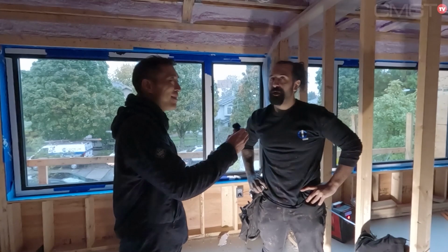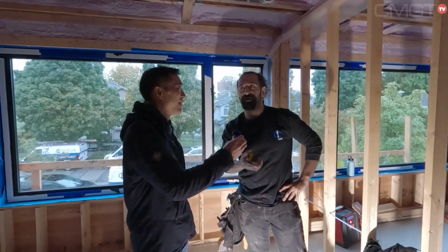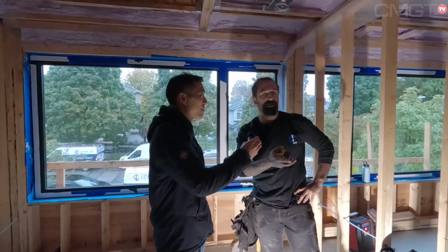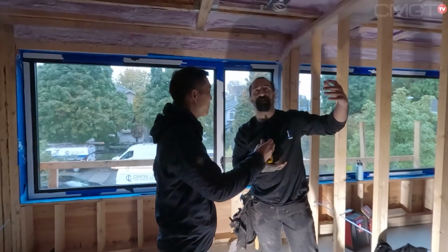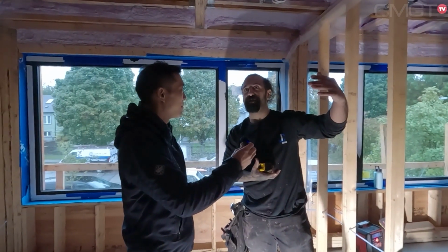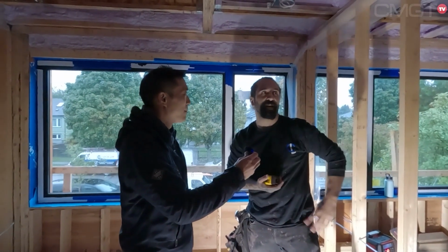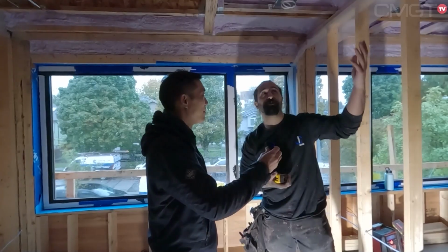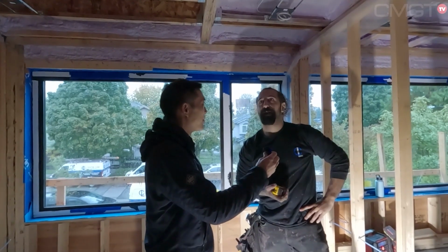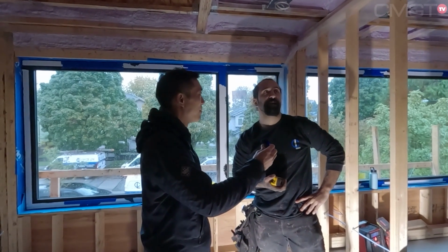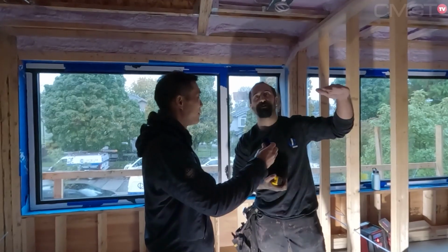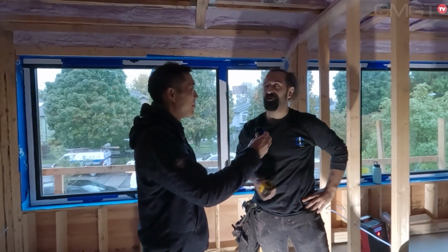Well, when we first go to a place, the first thing we have to do is find where to put our risers, and whether we can cover 8 feet from each side of a head or 9 feet from each side of a head. It's very important, and we try to always line up the lines. We like the plumbers and the ventilation guys to run their stuff high so we can run under them, and there will be enough room for insulation.